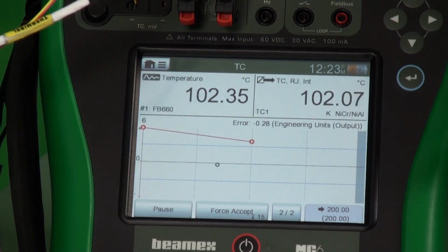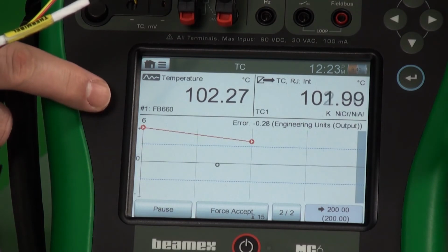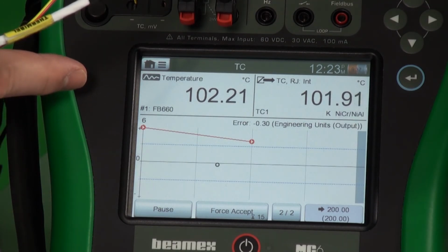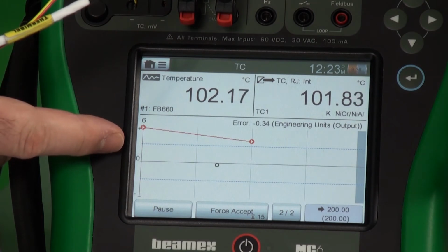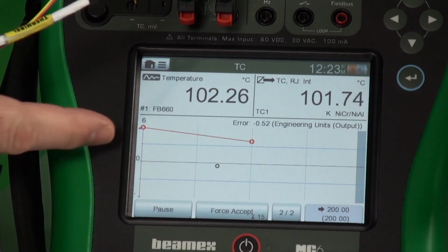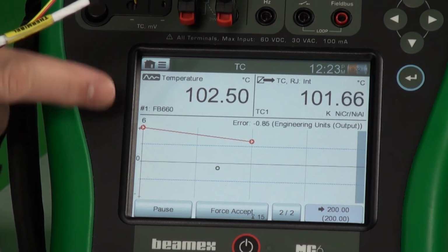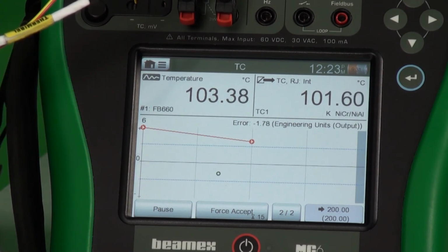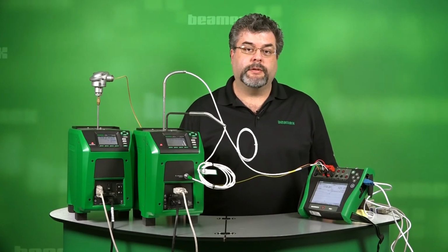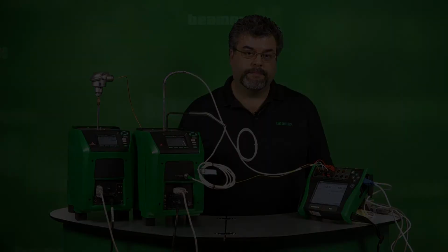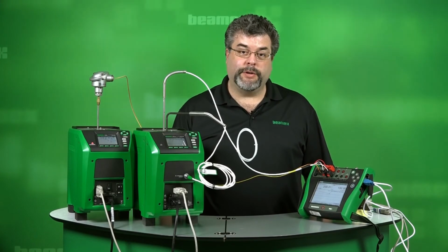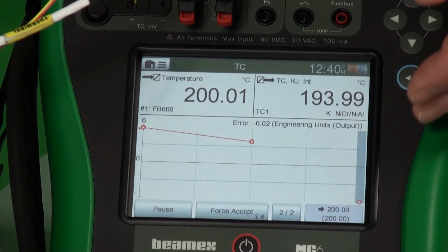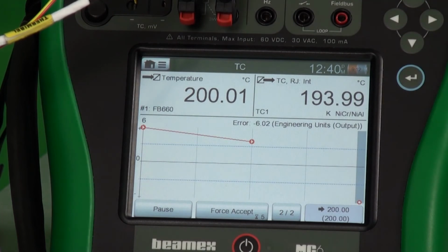Now this will accept this test point soon, and now we'll be going to the third and final test point of our thermocouple. But let me explain something. You can see that on the thermocouple, the lines are actually red, the dots. That means that each test point has failed so far. Now we have the 0, and the blue lines above and below represent our tolerance. As long as the dots are within the blue lines, then we know it's a passing test point. Now we'll wait for the final thermocouple point to heat up. We are coming up on our final point for the thermocouple. We can see that it's actually dropped below the 0, so we have error on all 3 of our test points.